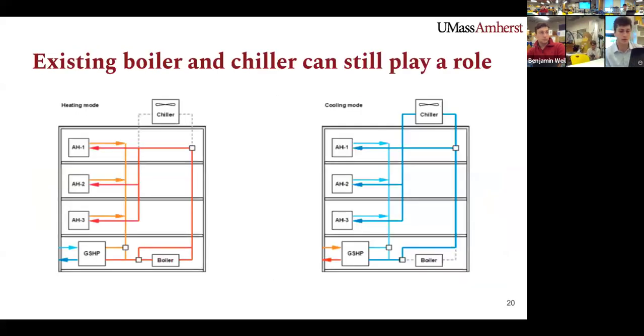So the existing boiler and chiller can still play a role. Under extreme circumstances, some extra cooling or heating may be needed. But fortunately, you already have that equipment in place with the boilers and chillers, so they can be integrated. These extreme conditions only make up a small percentage of the time, so using the chillers and boilers will allow you to spend a lot less money. Since this equipment is already in place, you do not need to purchase anything further and can just use what you already have.